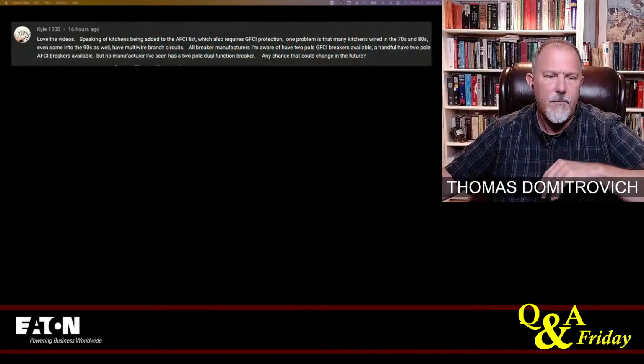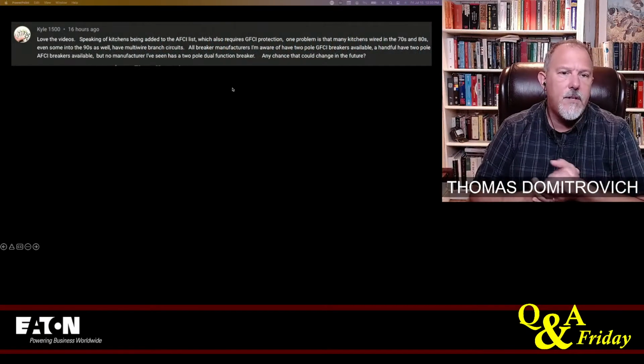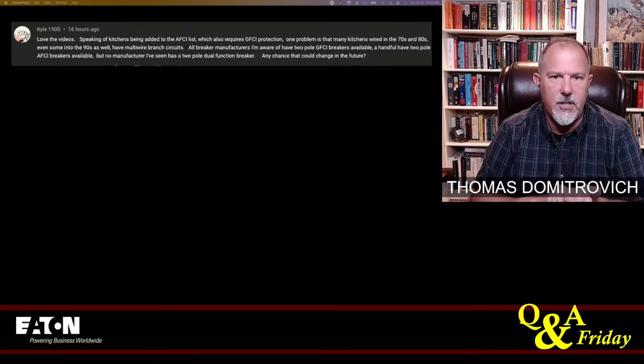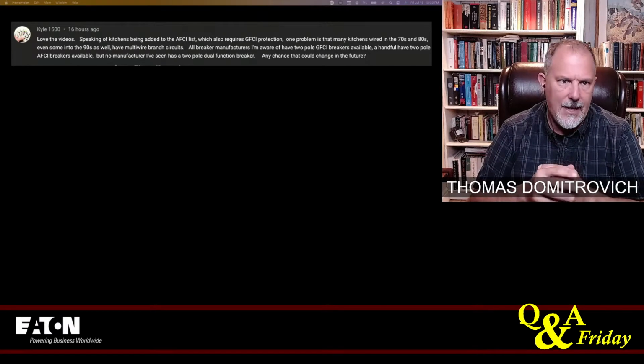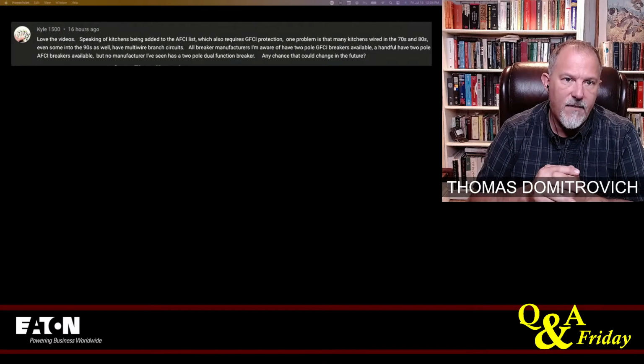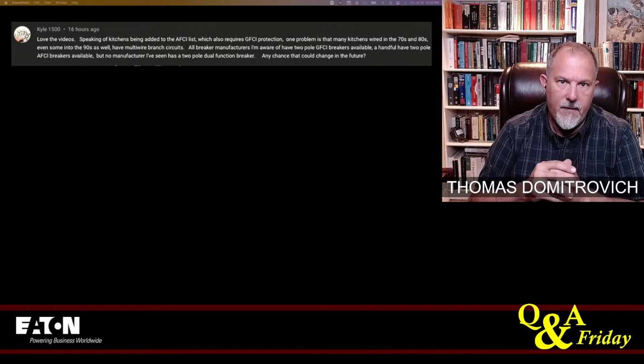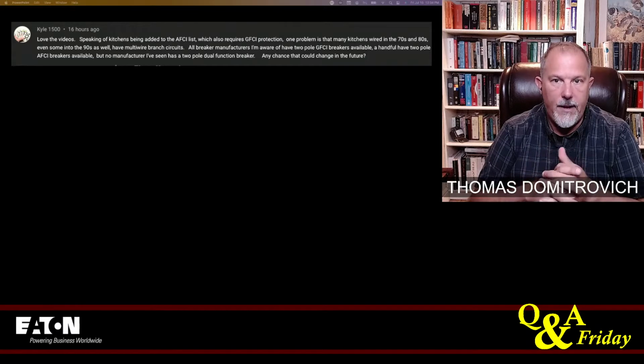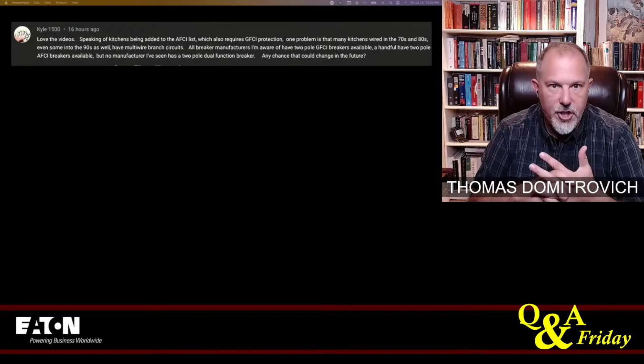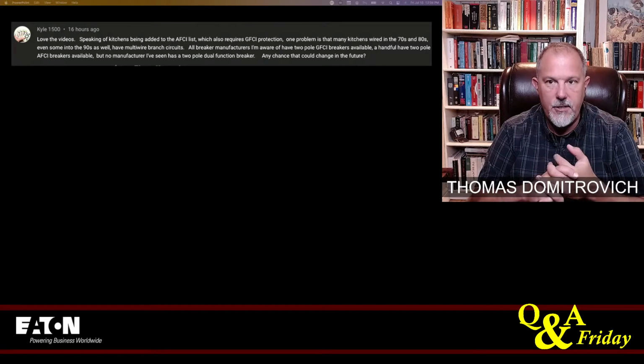Okay, so I did have a couple other questions. Love the video. Speaking of kitchens being added to the AFCI list, which also requires GFCI protection, one problem is that many kitchens wired in the 70s and 80s, even some into the 90s, have multi-wire branch circuits. All breaker manufacturers I'm aware of have 2-pole GFCI breakers available. A handful have 2-pole AFCI breakers available. But no manufacturer I have seen has a 2-pole dual function breaker. Any chance that would change in the future?